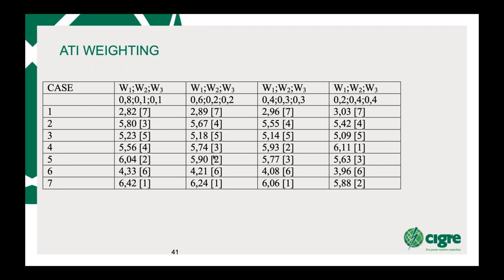Then what we did was use the weightings, where W1 is LCC, W2 is thermal rating, and W3 is the MVA SIL. You find that you need to look at a line which will give you, using various ratings, the best option. And these figures in the square brackets are the ranking. Interesting to note that case one, the quad zebra that we would use as a standard, came out virtually last in every single one of these options. In other words, the other options we looked at gave you a far better initial cost to MVA or thermal rating, as well as the SIL.